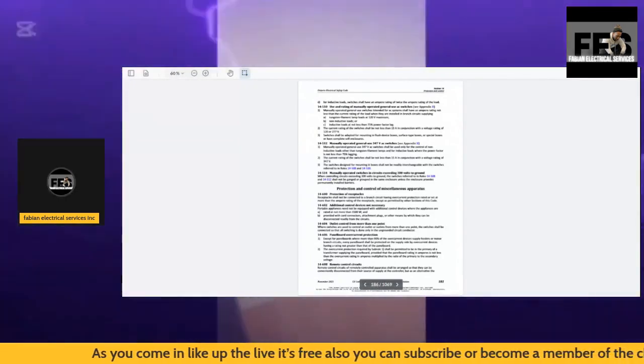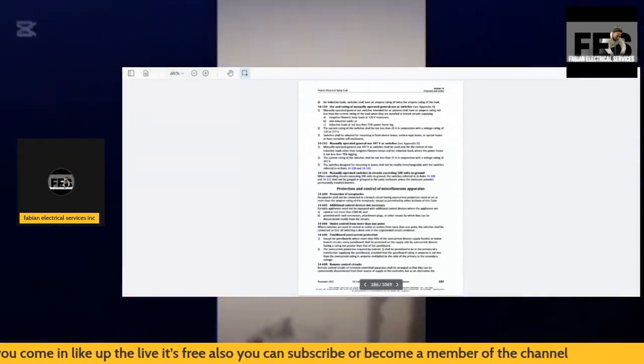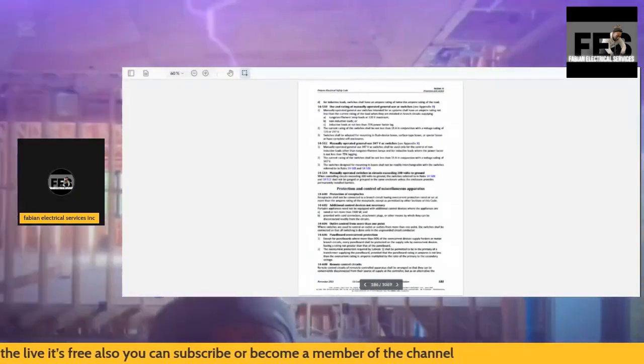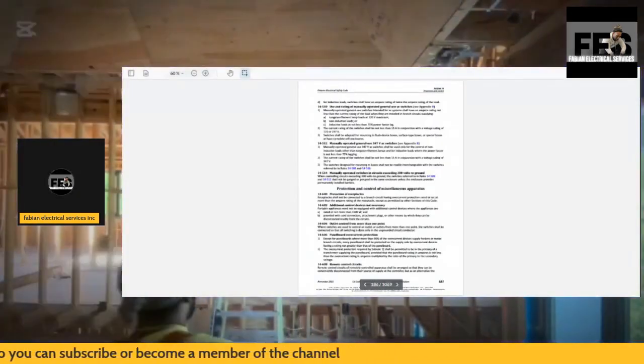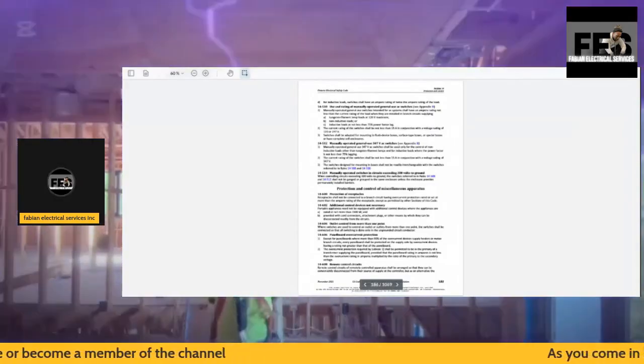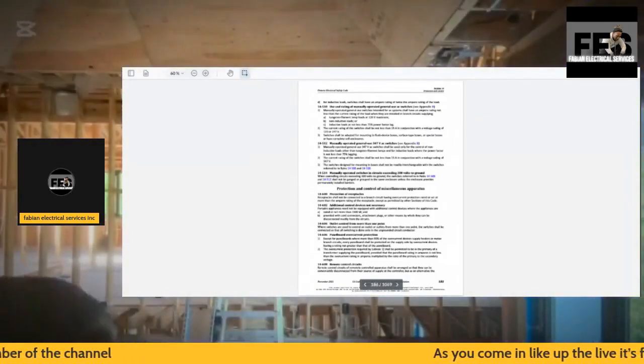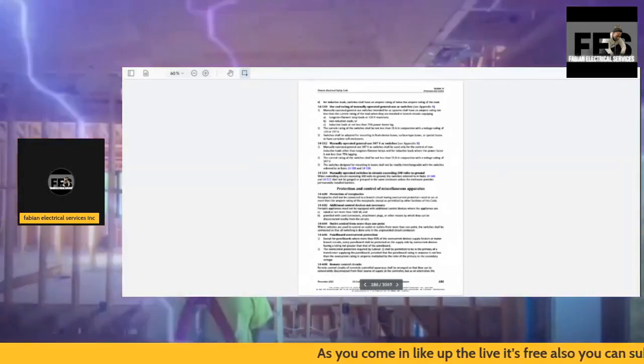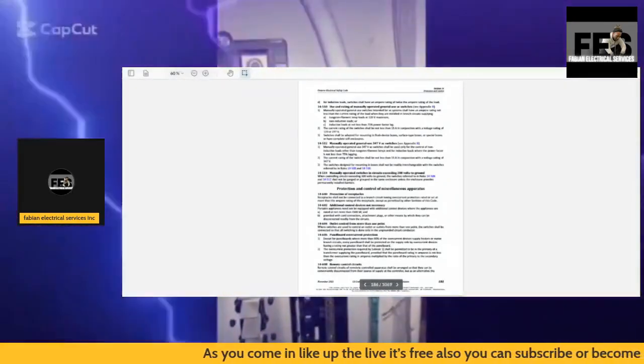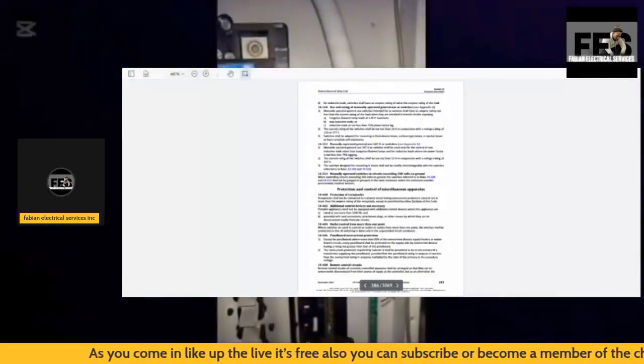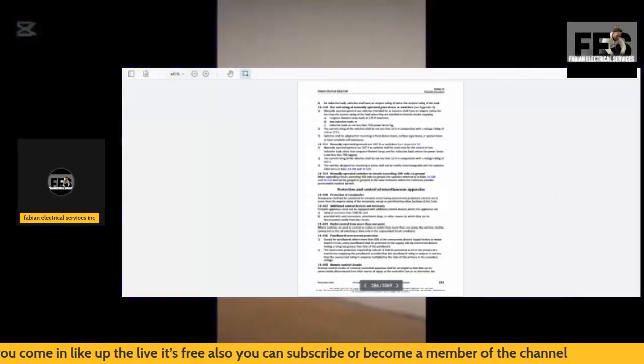The overcurrent protection required by sub-rule 1 shall be permitted to be in the primary of a transformer supplying the panel board, provided that the panel board rating in amperes is not less than the overcurrent rating in amperes multiplied by the ratio of the primary to the secondary voltage.